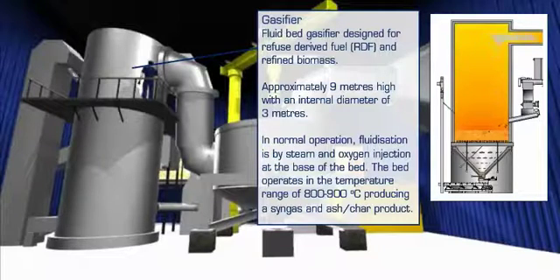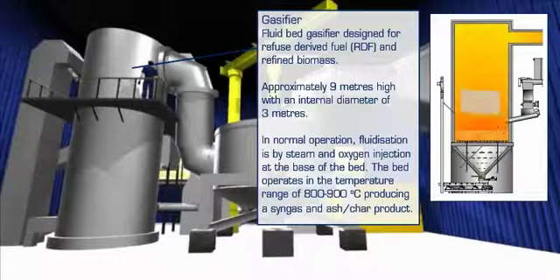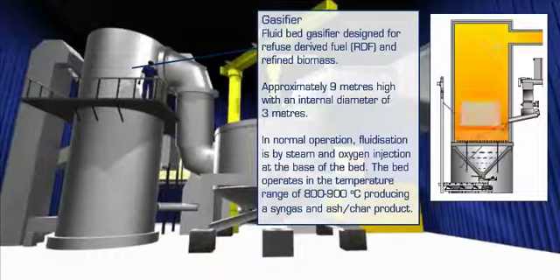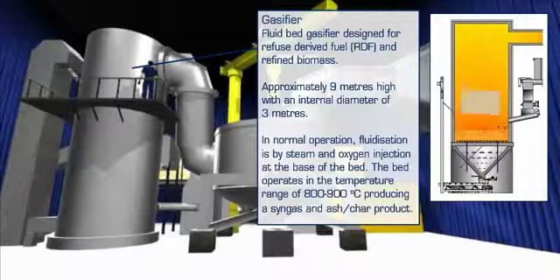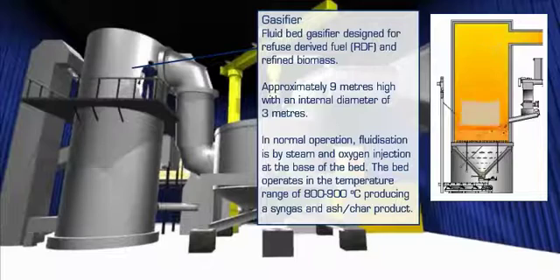To give you a sense of scale, the gasifier is approximately 9 meters high and has an internal diameter of around 3 meters. In normal operation, the gasifier's sand bed is fluidized by steam and oxygen injected through nozzles at the base of the bed, so as to maintain a starved air atmosphere inside the gasifier. Refuse-derived fuel or RDF feedstock is fed into the gasifier slightly above the bed and is quickly converted into a syngas that leaves from the top of the gasifier.